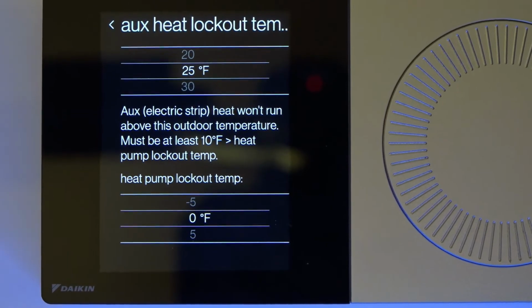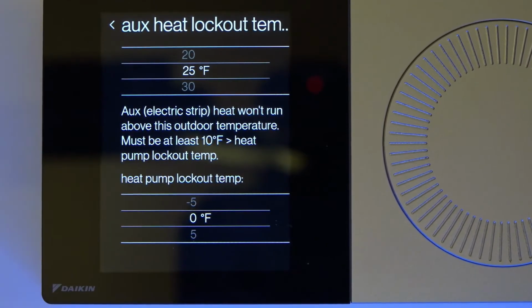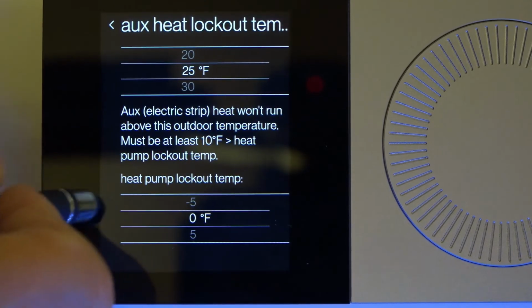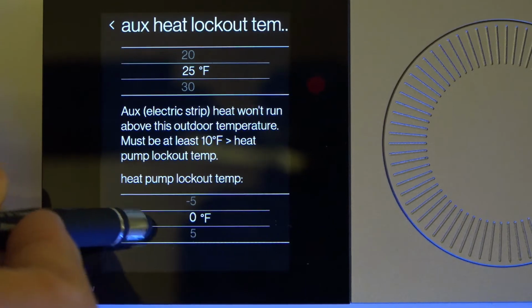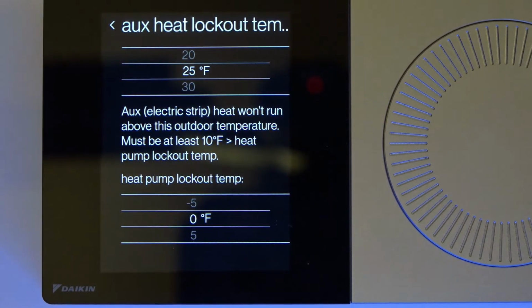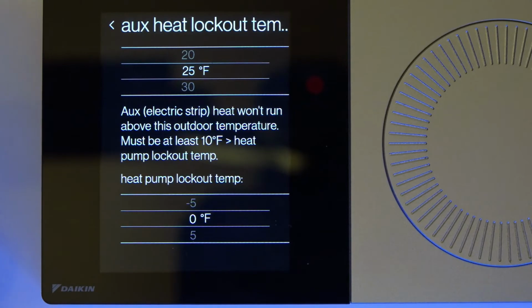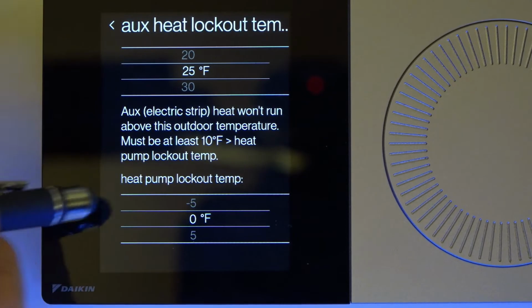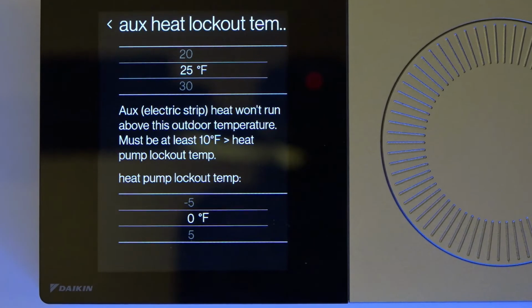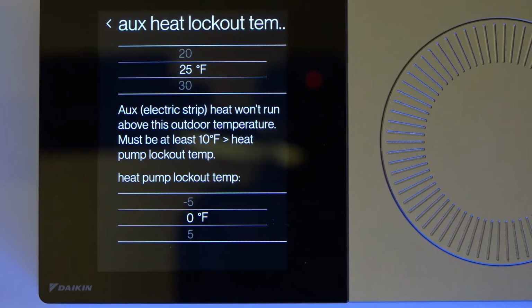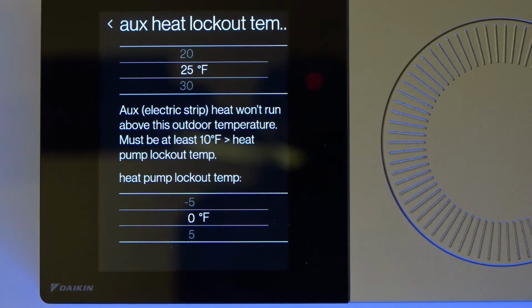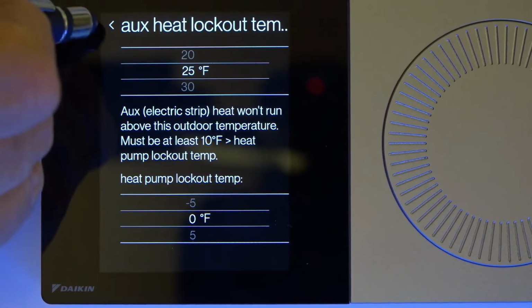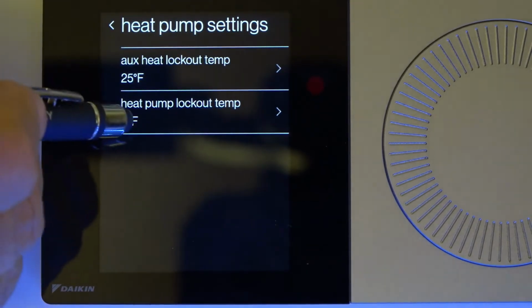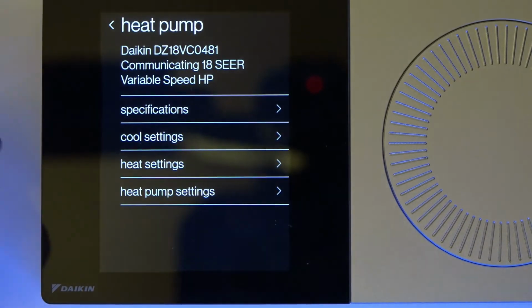So it's all about comfort with the inverter, so I can dial the system in to give the customer what they need. Now, heat pump lockout, that's our compressor lockout. If I was doing dual fuel, that'll allow me to set the balance point of where I want it to switch from compressor over to a gas heat. But in this case, I usually take it down to 0 here in the southeast, because there's still good heat and this system's pretty efficient. Down to 0 we can still grab a lot of heat out of the air with the system, no problem. Okay, that takes care of that section.